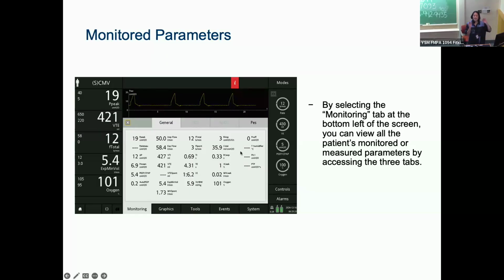The one caveat is that in the ventilator, these numbers, particularly the plateau pressure, are derived from micro-occlusions that occur during the breath that the machine is making. It is not from a measured plateau pressure that the respiratory therapist is making. And so, therefore, the calculations made from that plateau pressure, including the resistance, the compliance, and tau, are also approximations of a number.